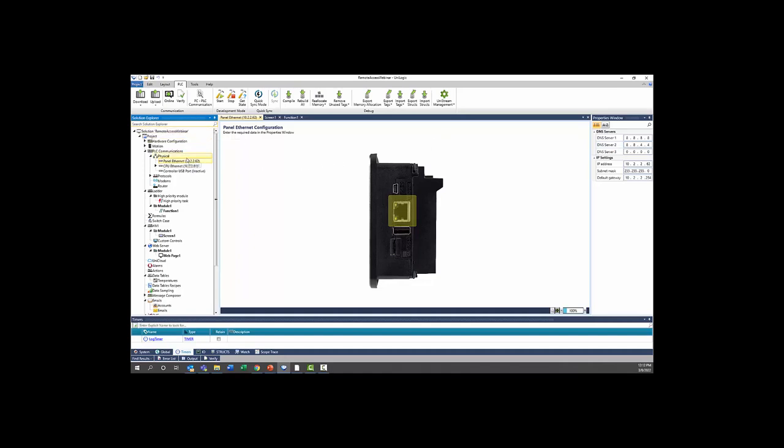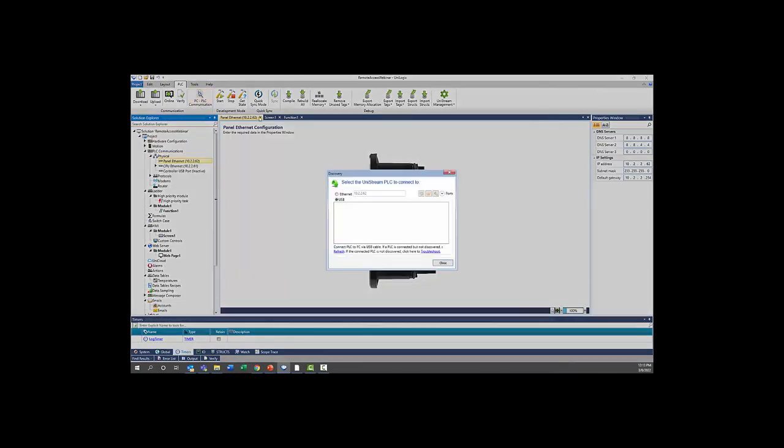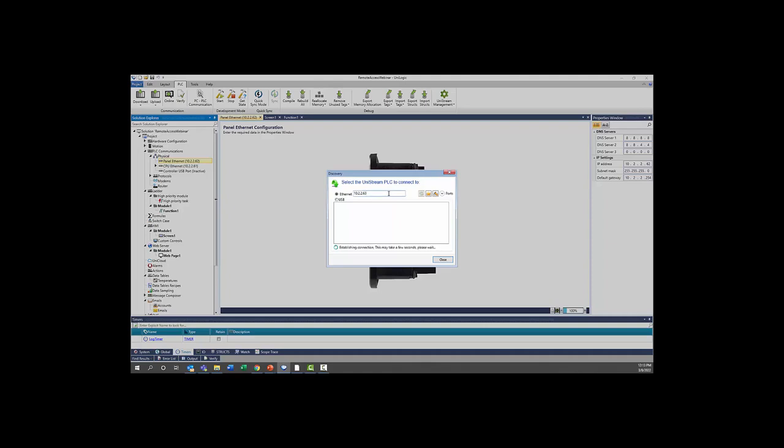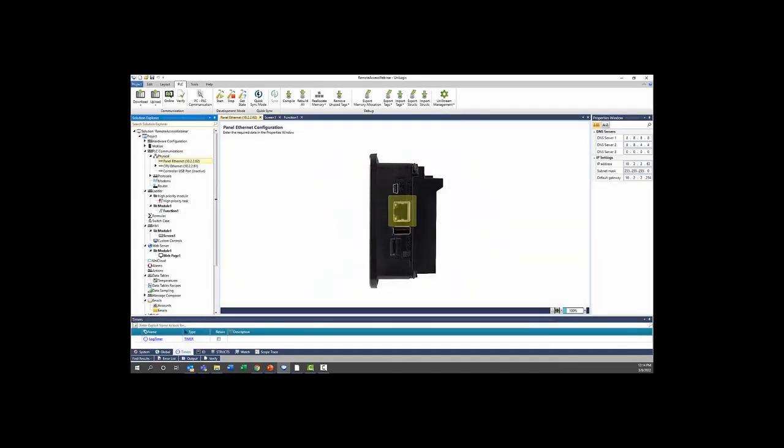So just to test to make sure that you have connection, once you have downloaded this project to your PLC, you can go to PC, PLC communications. You can select Ethernet, and you're going to put in the IP address of that unit. If you have a connection, a green check here, you'll have connection. However, if we change this to something else and we press the refresh, it's going to wait a few seconds while it tries to connect. And either this is going to take a long time and never finish, or in that same area where that green check mark is, you're going to see a red circle with an X in it.